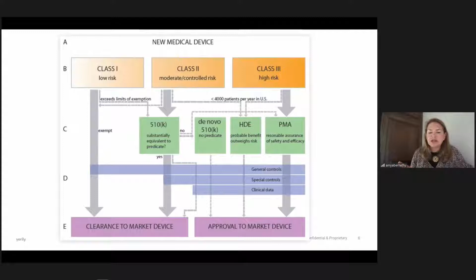Now importantly, first classified in 2014 through the International Medical Device Regulators Forum was this idea that there's an evolving landscape of software as a medical device. So this is not the software used to run a hardware medical device. So for example, this is not about the software used to run a pump that delivers IV fluids. This is actually the regulation of software and algorithms where that is the predominant product. So for example, it could be an algorithm that's an in vitro diagnostic. It could be general purpose algorithms that are intended to run on any kind of computing platform where the computing platform is not intended for medical use. Or these could be software products that are included in the context of other medical devices. And this landscape was really codified in an international document in 2014.